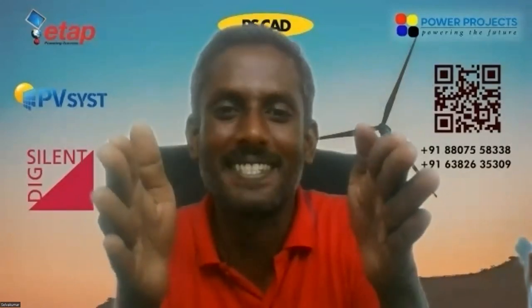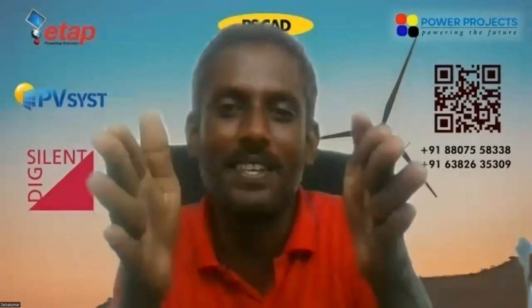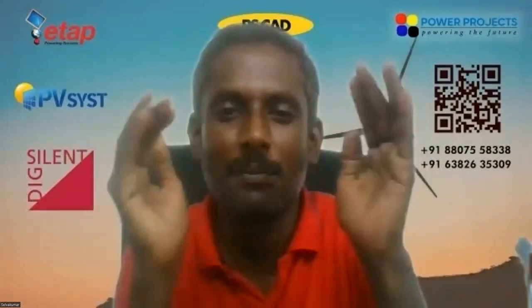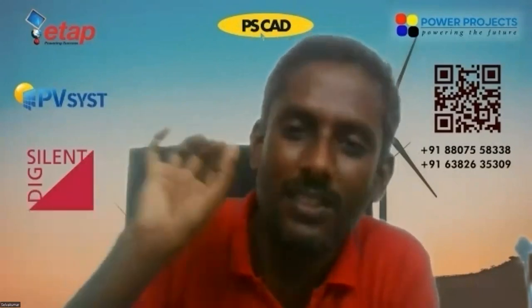If I keep this, what happens? The phase to ground voltage is 400 by root 3 kV. But if I keep these two conductors this close, it ionizes the air in between, and that air starts conducting. It's not a fault, it's an arc: the air is ionized and there is a conductive path, but not with zero impedance; it is with some fault impedance. That's not corona, to make it very clear. Corona is slightly different. The current flows through this ionized air. That's the real reason why I cannot move my hands very close to a 400 kV system.